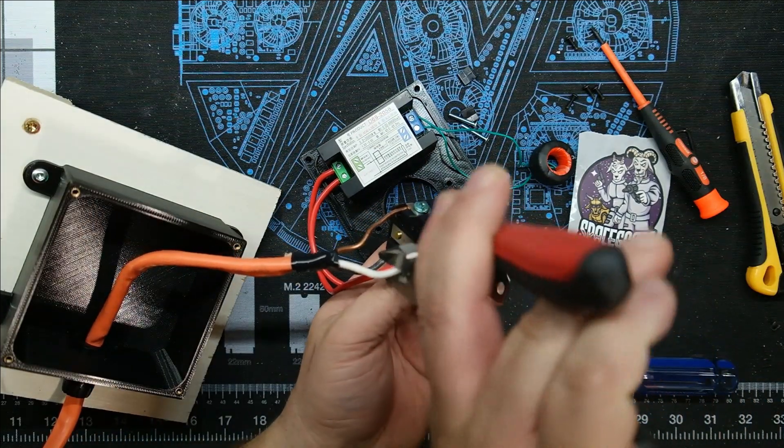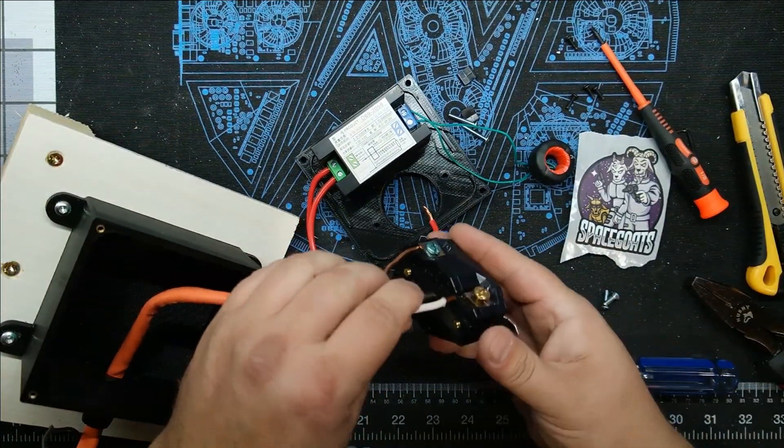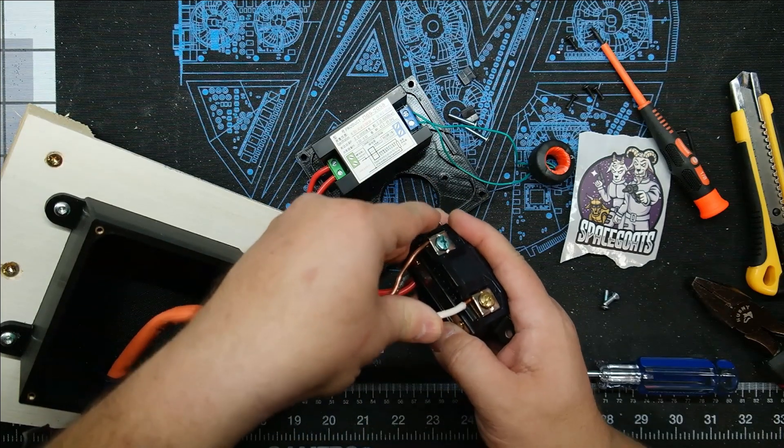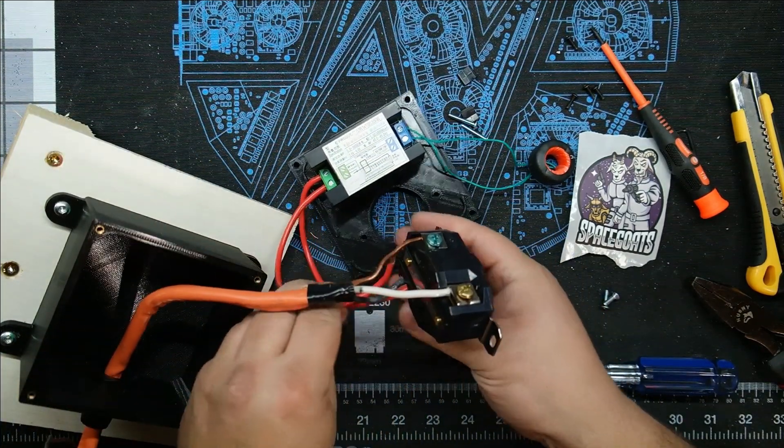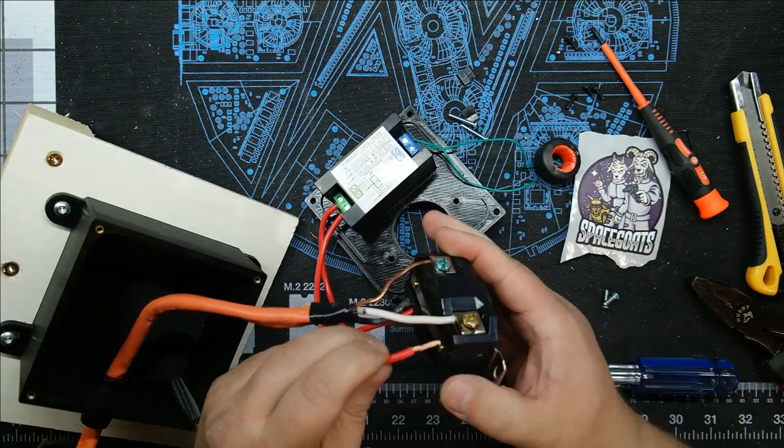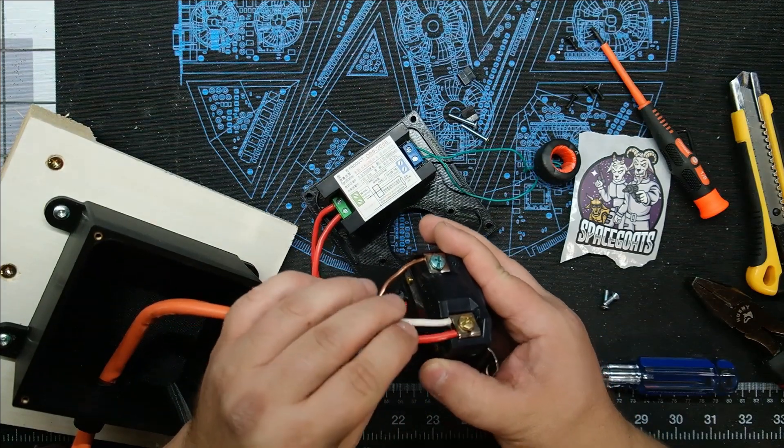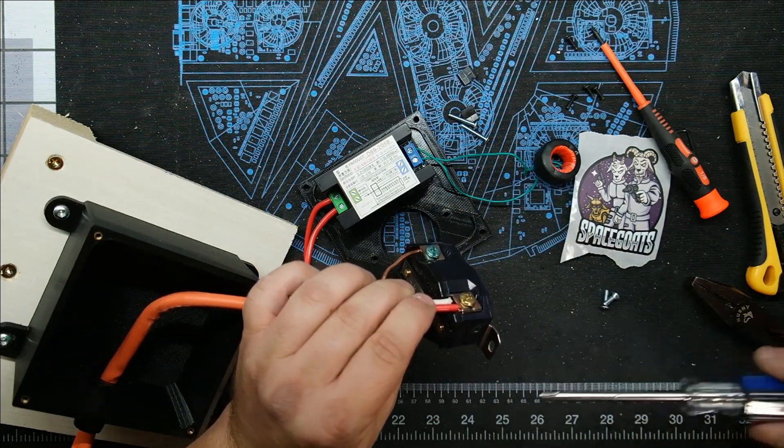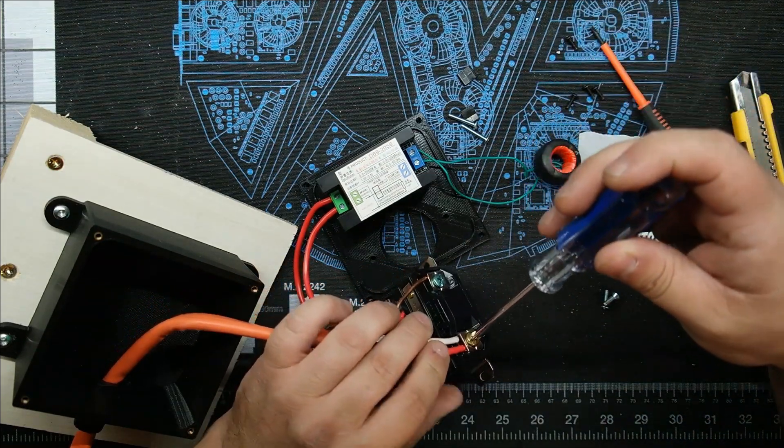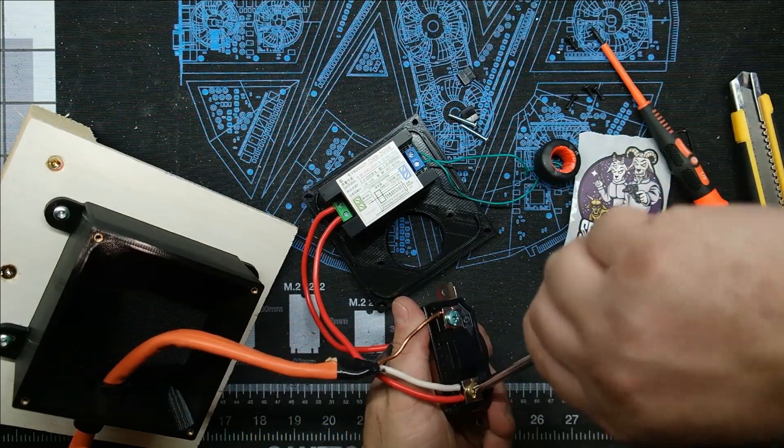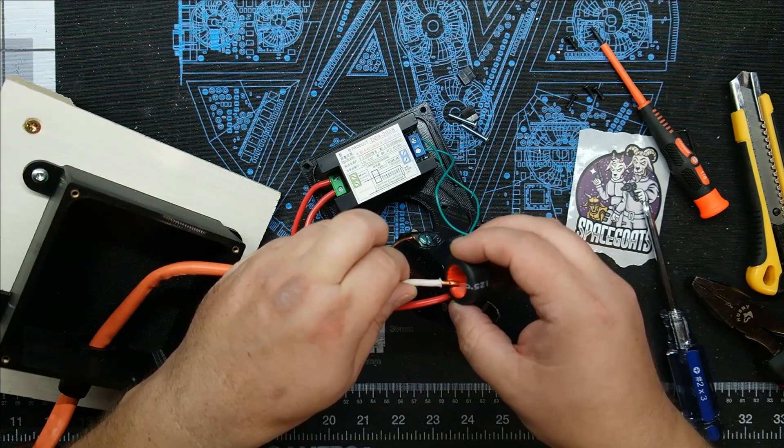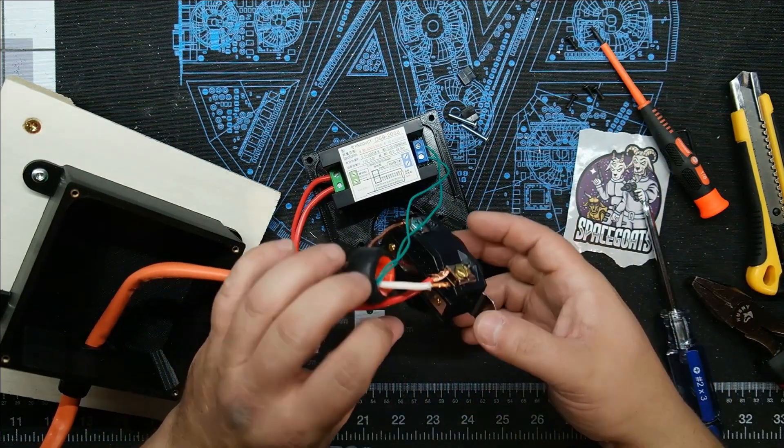This really helps bending this wire. There we go. Let's bring this wire up over and around. Make sure there's no frays. Last thing you want is 240 volts shorting out somewhere. You can see how you can get a hot and another wire on both sides. Now tighten that down really good. The coil must go through one of the hots and that's how it reads.